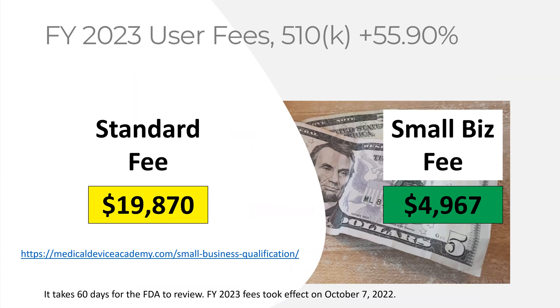Another thing that changed is a big price increase. Just like gas prices and housing prices going up, FDA user fees have gone up. Most user fees went up by roughly 17.9%, but the 510k fees went up 55.9% — a huge increase. The de novo increased at the same rate as others, about 17.8%. The small business fee is now almost $5,000 and the standard fee is $19,000. If you apply for small business qualification and the FDA grants it, you will save almost $15,000. That's a very big increase that's going to affect some companies.